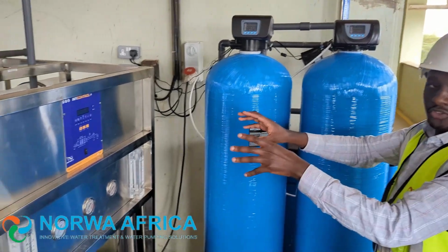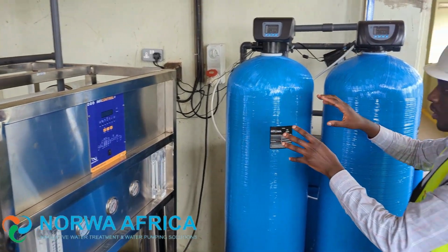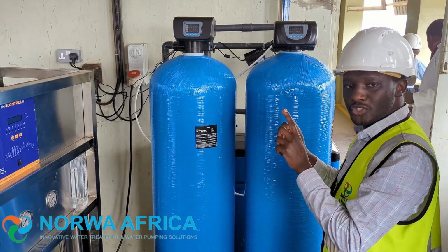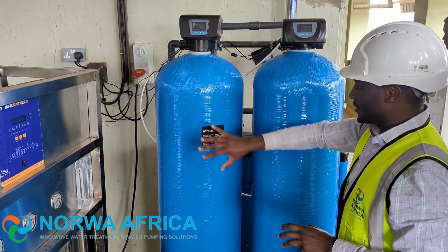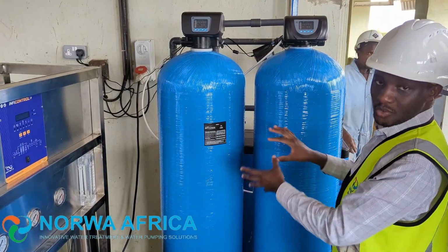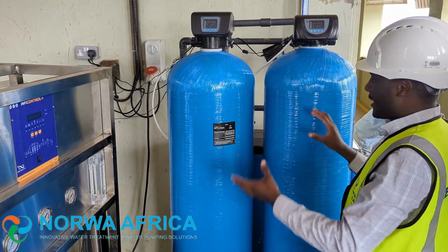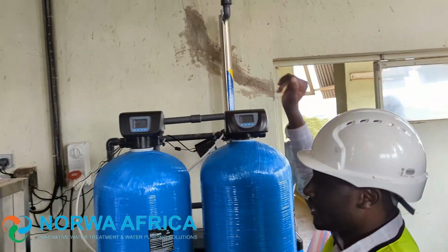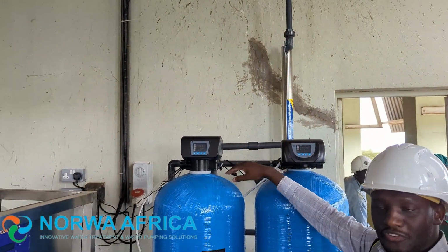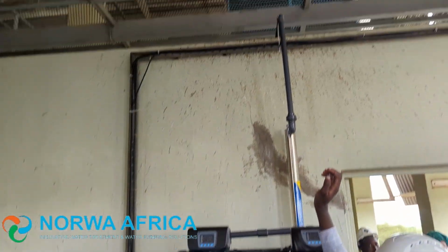After the water comes from the reverse osmosis, we want to make sure that the TDS goes all the way to below 5 milligrams per liter. So this is what helps us to achieve those particular numbers. So after here, the water goes through the UV, and then from the UV, it goes to the treated water tank.